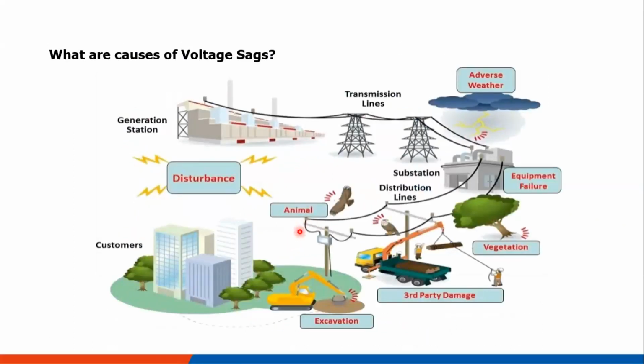So, what causes voltage sags? Any disturbance can cause voltage sags, such as weather, lightning. Lightning striking the bare conductor of the transmission line can cause voltage sag. Equipment failure. In our substation, we have so many equipments. Equipment failure, the VCB, the transformer, any equipment failure can cause voltage sag. Vegetation, okay, a tree falling onto the bare line or any other lines, insulated line, can cause voltage sag.